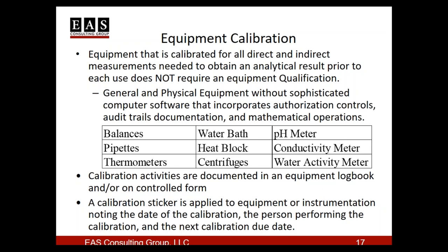All of those calibration activities will be documented in the equipment logbook and/or on a controlled form that can be incorporated into a logbook. A calibration sticker would be affixed to the piece of instrumentation to demonstrate that the calibration was done, who did it, when it was done, and what the next calibration due date is. This is a requirement in 111 - the piece of equipment indicates to the analyst or microbiologist in the laboratory that yes, I'm using a piece of equipment that is appropriate and suitable for use.